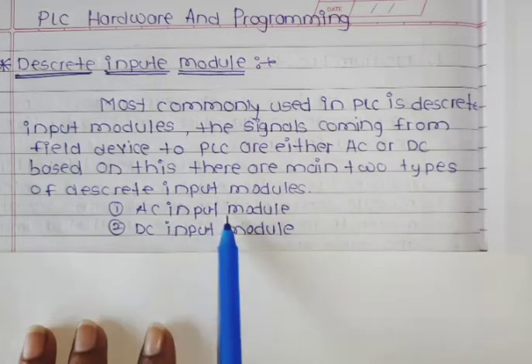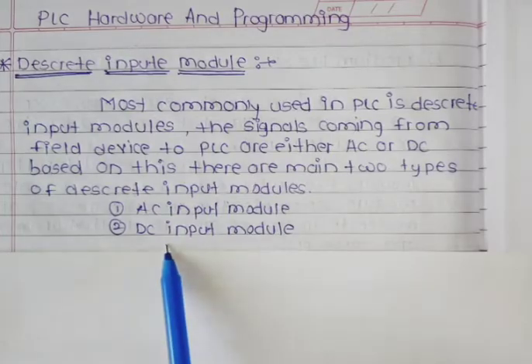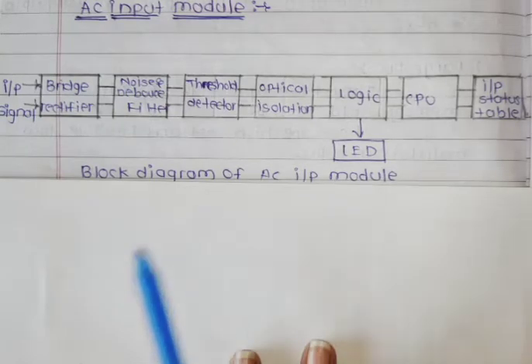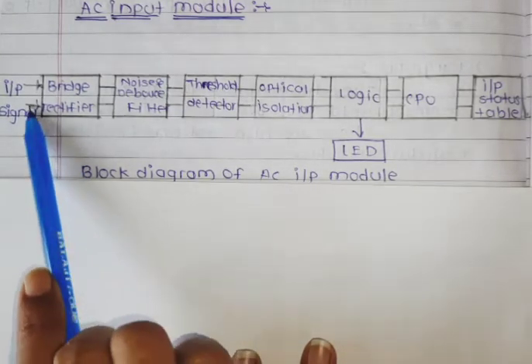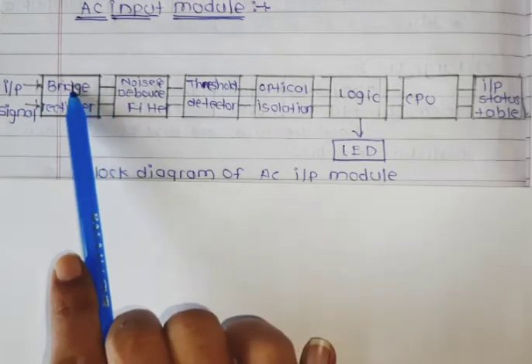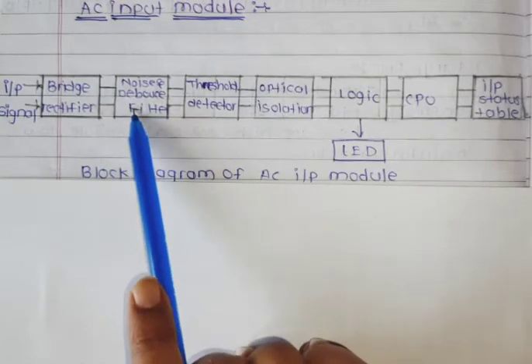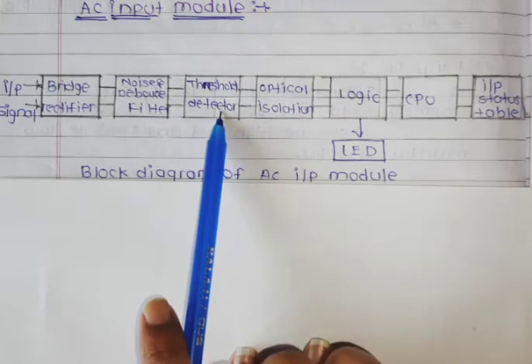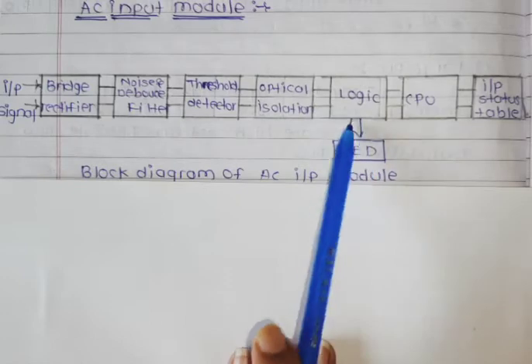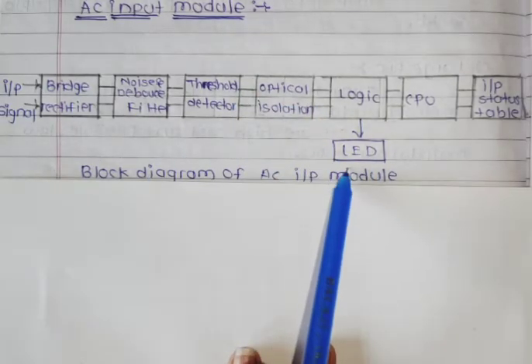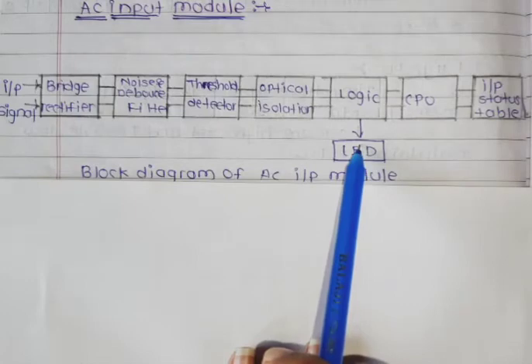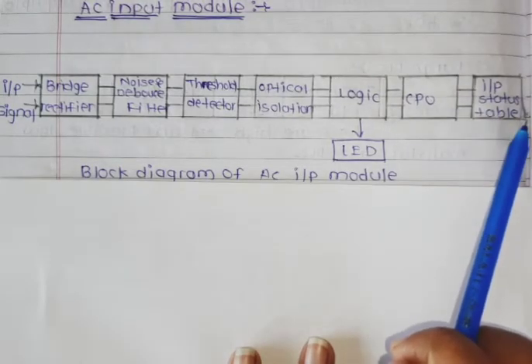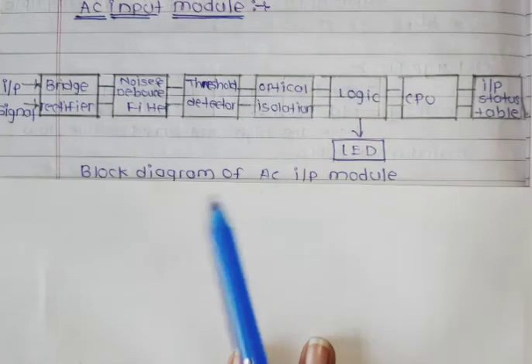Today's lecture covers the AC input module in detail. We see the block diagram of the AC input module. In the block diagram, there is first the input signal, then a bridge rectifier, followed by a noise and debounce filter. After that there is a threshold detector, then an optical isolator and logic section which also has an LED as output. Finally, there is the CPU (central processing unit) and the input status table.